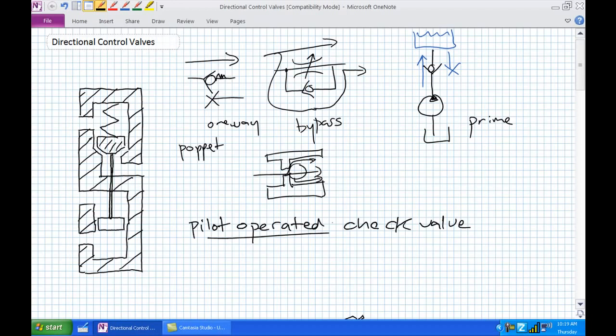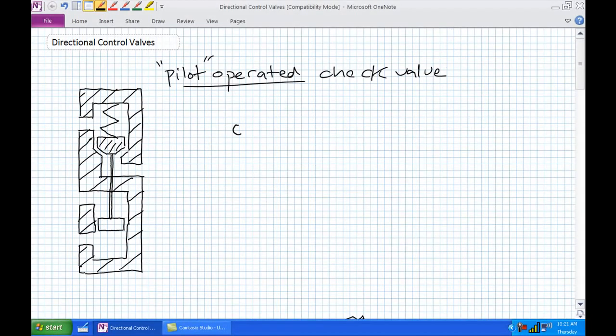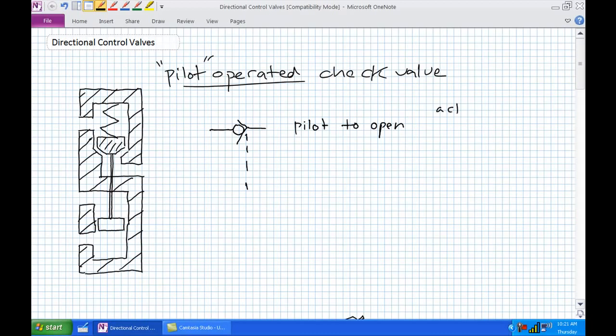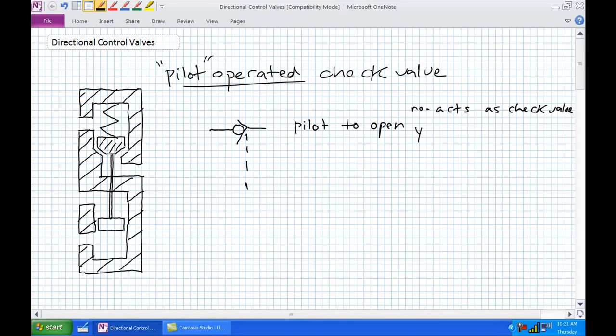A pilot-operated check valve looks like a standard check valve with a pilot line symbol coming to it. This is a pilot-to-open check valve. With no pilot signal, it acts as a check valve — allows flow in one direction, blocks it in the other. When there is a pilot pressure signal, it opens up, allowing fluid flow in both directions.